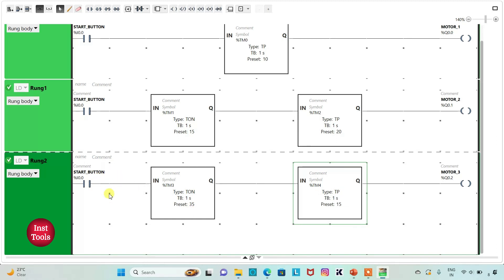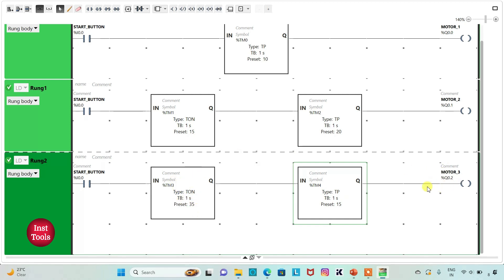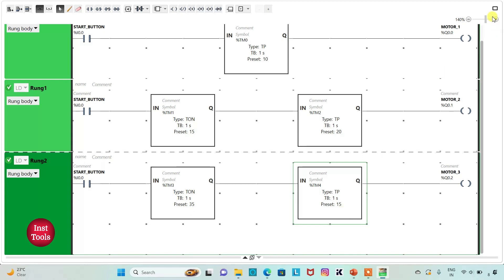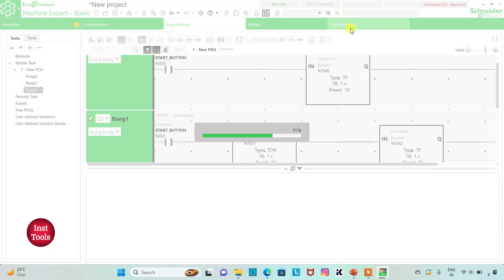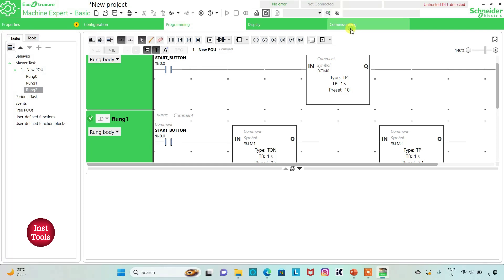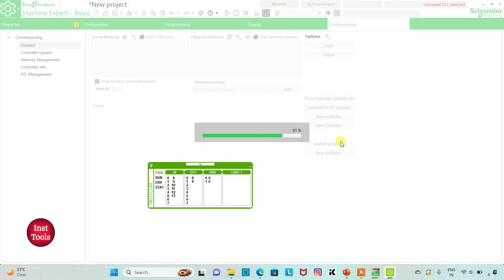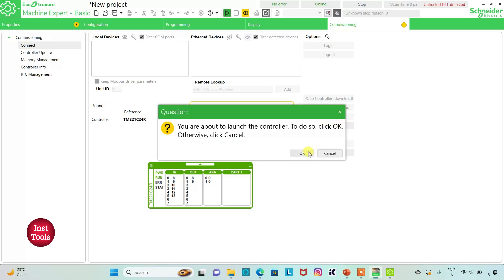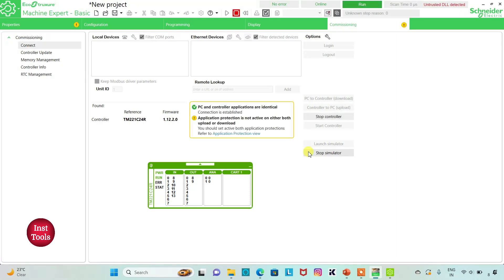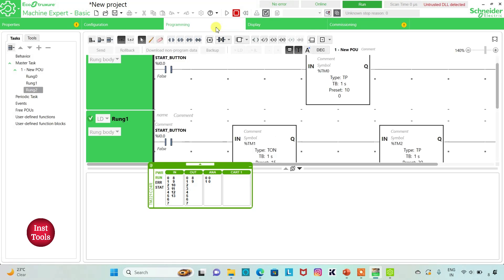So when the start button is turned on, there will be a delay of 35 seconds and then motor 3 will be on for 15 seconds. I will exit full screen mode, compile the program, and then go to Commissioning and launch the Simulator. I will start the controller — click OK. I will go to the Programming tab and enter full screen mode.